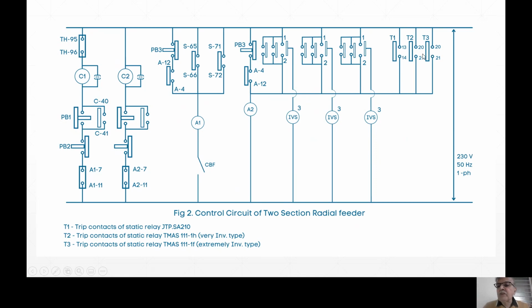This T1, T2, T3, 13, 14, 20, 21, they are for static relays. So static relay also can control the relay A2 and can trip the contactor C2, right? So C2 can be tripped if there is a fault in second section. If there is a fault in first section, then this 65 and 66 are main trip contact. Another very important thing, 71 and 72 is there, right? That is relay failure. I cannot fail the relay, obviously, because then I cannot use it for second group, the second batch, another year student. Therefore, what will I do? I will make the auxiliary supply off. So 71 and 72 will get connected and A1 will operate. A1 operating, breaker C1 will trip.